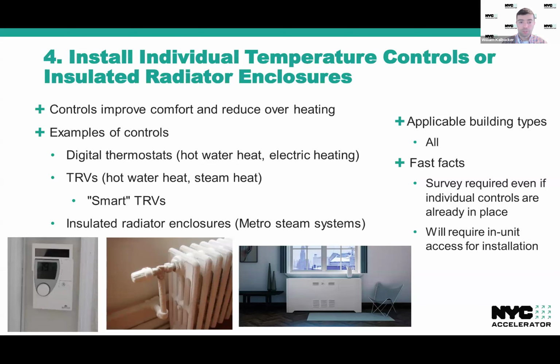And there are a couple of different examples of controls that can be installed here, depending on the heating system that the building has. So digital thermostats that you might see on a wall might be appropriate for a hot water heated hydronic building or an electrically heated building. For hot water and steam specifically, something like a TRV, a thermostatic radiator valve, or a smart wireless TRV might be appropriate. And for buildings that use a metro steam system, an insulated radiator enclosure, which is basically a housing that sits over the entire radiator, is also a means for compliance here.